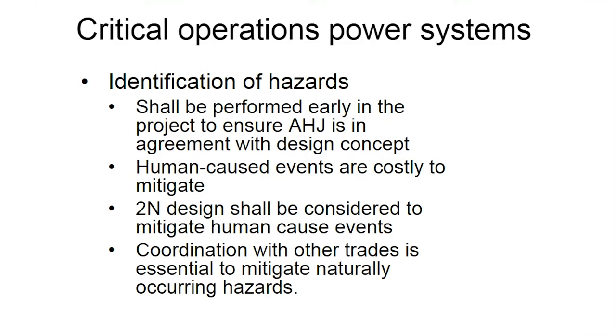One thing you get out of this is that when you get into a job like this, and it was already decided, you start the process of designing the facility. The first thing you try to do is assess your risk, and identify which ones are your risks. You need to make sure that the AHJ agrees with your design concept. There are many ways to comply with 708, so I would definitely advise having early meetings with your AHJ, your fire marshal, and your city reviewer, so you make sure the concept you are using is an approved concept. Especially if you're not using ATSs and you want to use a 2N system, because now the 2N system overall becomes your ATS, and it's kind of tricky. You need to make sure your AHJ is on board with that.